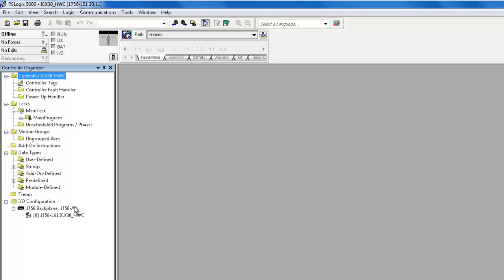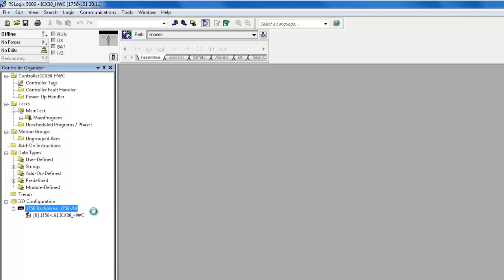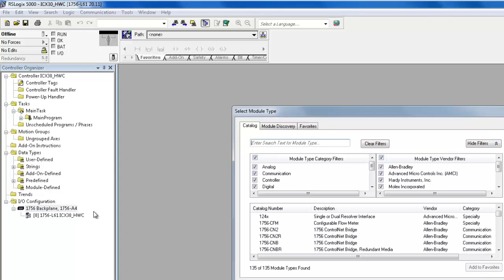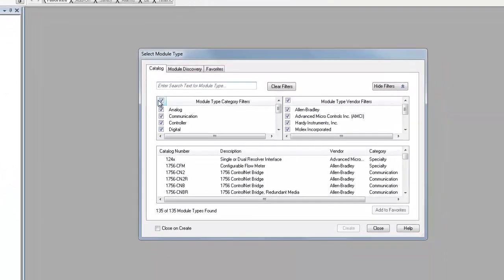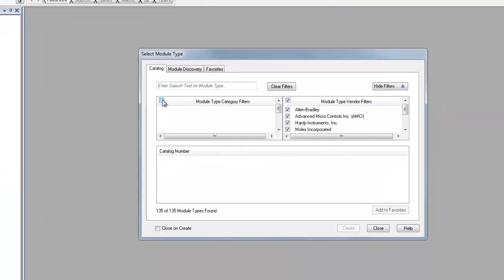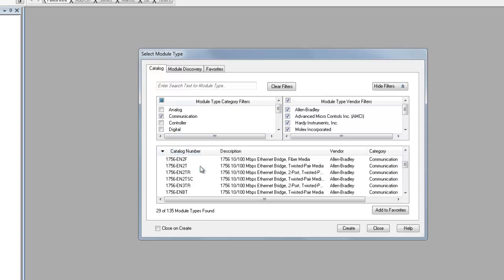Next, we need to create an Ethernet path to get to the ICX30HWC. If you are using a processor that has an Ethernet bridge already installed in the project, you do not need to do the following step. Right-click on the backplane and click New Module. Uncheck the Module Type category filter, then check Communications. Highlight the 1756-EN2T and then click Create.